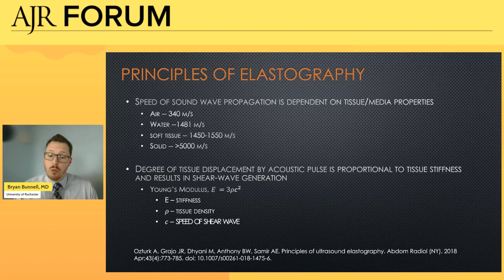transducer. And so we can do some algebra to then calculate a representative tissue stiffness value using what's called Young's modulus. You can see the formula there, where E is the tissue stiffness. We have a factor of 3. And then that's multiplied by the tissue density, which is assumed or held to be constant. And then C is the speed of those shear waves that are generated by the displacement, and that's what's measured by the transducer.